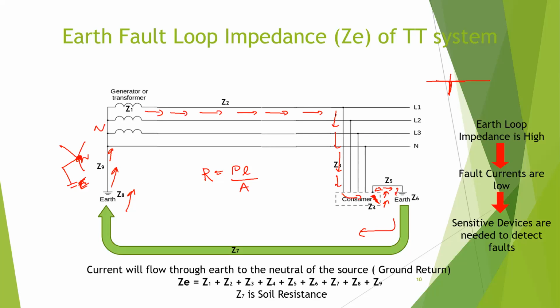Okay, so we are now coming towards fault condition. So earthing is done to protect you from faults. So if there's an enclosure energized, we should identify that, and we should keep that enclosure's voltage at a safe level, so that you will not get a shock. Usually we have, I am coming to that in a few seconds. We are not going to keep our connection like this. If you have this condition, we are going to immediately trip the circuit. So I am coming to this now. So okay, you will understand this. Is it possible to pass current for a long distance because the transformer is far away from the consumer?